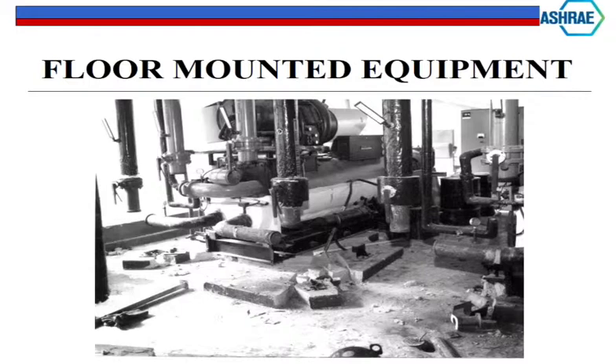So the action of a plinth, in most mechanical rooms, is just to raise the equipment so if there's a leak somewhere, it's not sitting in water. That's the basic premise, okay? But it's also your structural attachment to the rest of the building, all right? So what you have is, in this case, about 200 millimeters of concrete, but it wasn't attached to anything, and it wasn't reinforced. So basically what you made was this big plain inertia block, and then you bolted the equipment onto it, right? It had seismic snubbers. They're way out there now. Not doing any good though, okay?